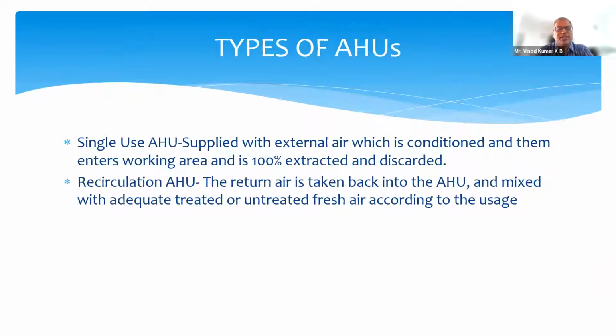Coming to air handlers, generally we have two kinds of air handlers. One, a single-use air handler, and the other one is a recirculation air handler. In the olden days, we have seen operation theaters where the air handlers are 100% fresh air handlers. What do you mean by that? A 100% fresh air AHU is basically taking in fresh air from outside. It's filtering the air, cooling, and then putting the air into the theaters. And the entire air is then extracted and discarded outside. So the air is only used in the theater or the ICU only once. So this becomes a single-use air handler.